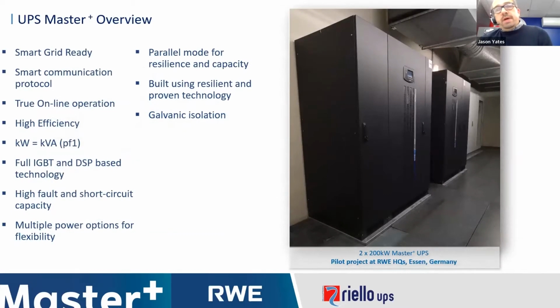So the key part was obviously the UPS system. The photo there on the screen was the 200 kilowatt test machines that we put into the pilot project in Germany. These two machines, which were developed for this project, are smart grid ready. They offer smart grid communication protocols. They're true online UPS systems. They're highly efficient. They're unity power factor machines, so the kilowatt and the kVA are the same. They're full IGBT and DSP based technology with high fault and short circuit capacity, multiple power options for flexibility, parallel mode for resilience and capacity, and they're built on existing resilient and proven technology, and they offer full galvanic isolation.